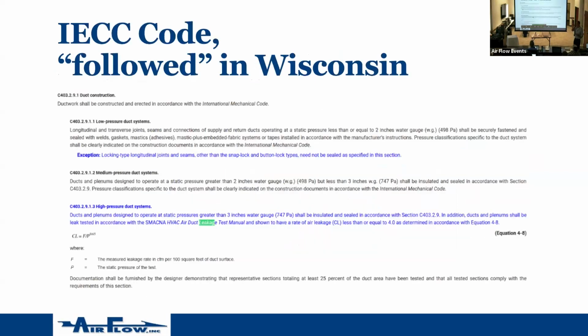Wow, that's really small print. Hopefully you can read this. For the first time, I'm going to show you this equation, CL equals F over P to the 0.65 power. If you remember old high school math, you need to turn your iPhone calculator sideways to do this calculation. Well, what's F? F is the measured leakage per 100 square feet of duct. P is our pressure, and CL is the class. We're going to dig into this too.